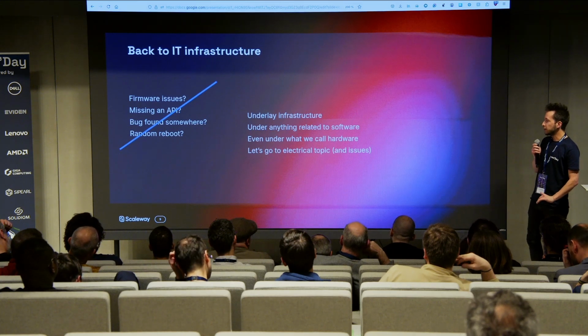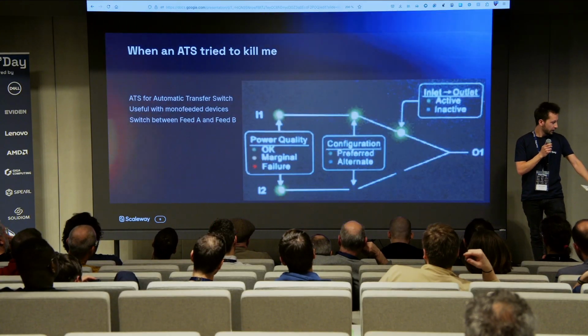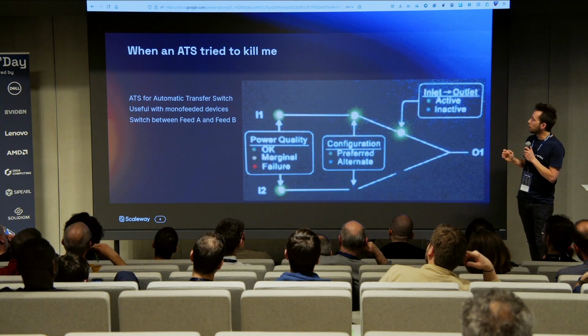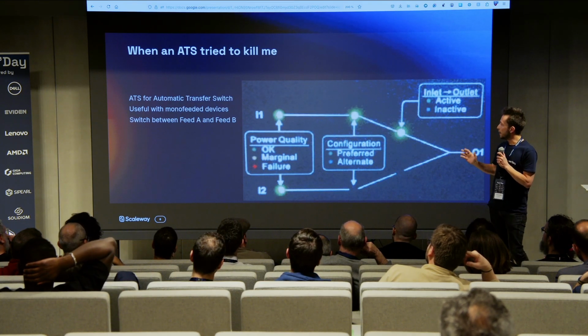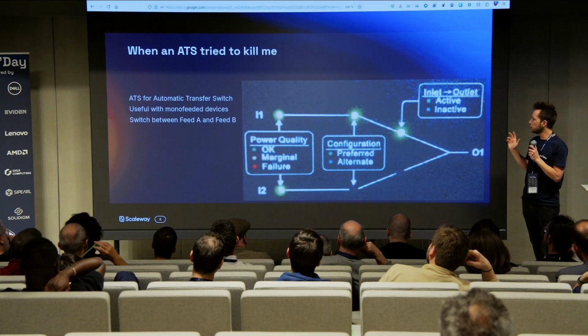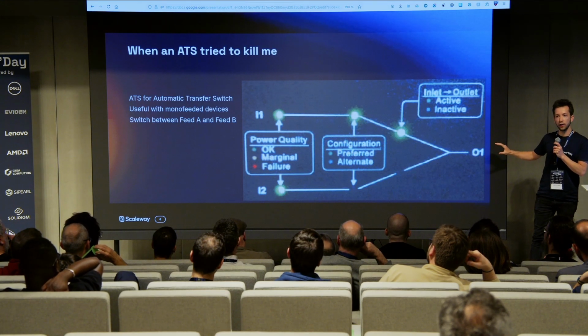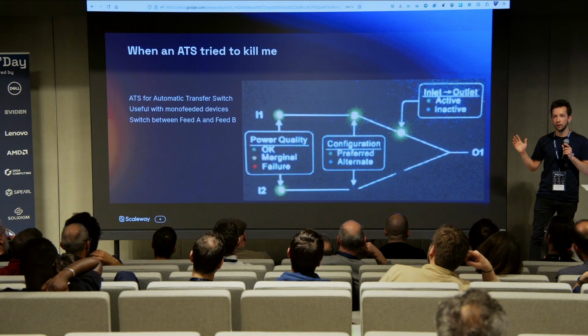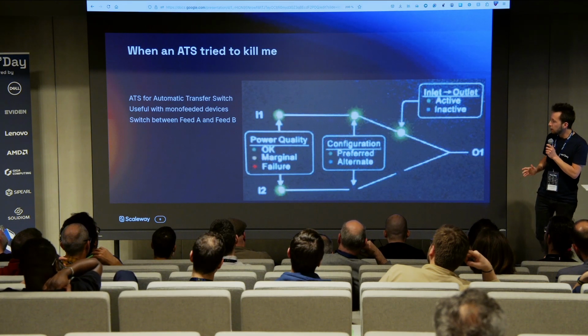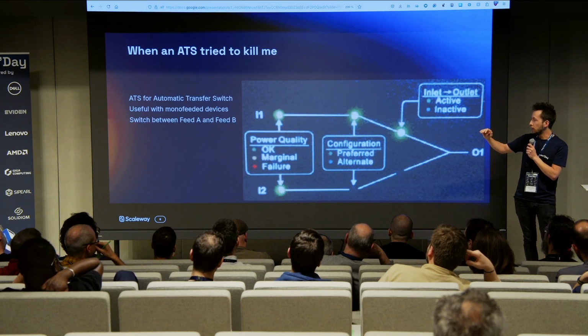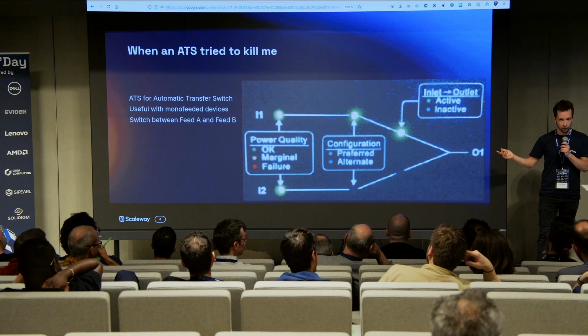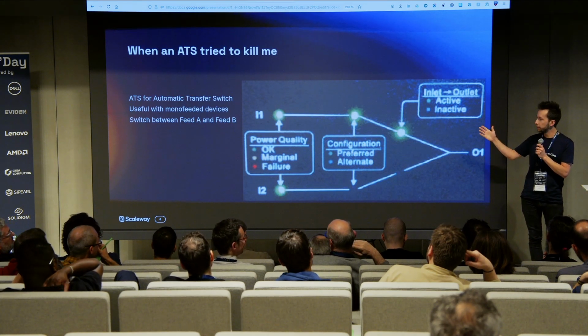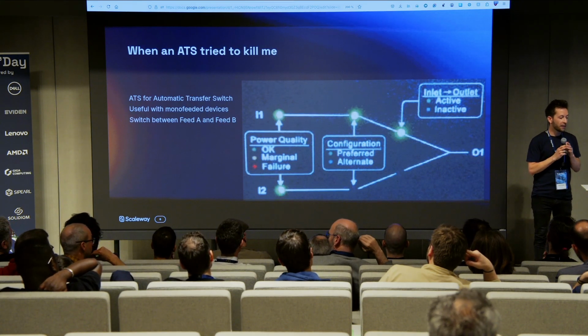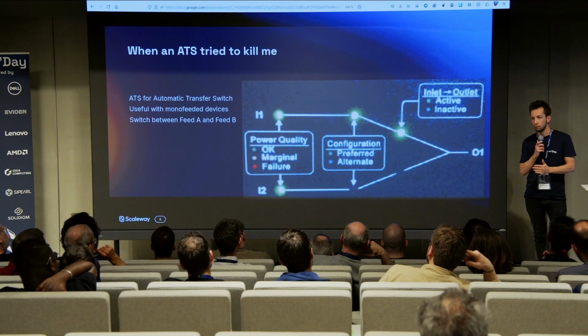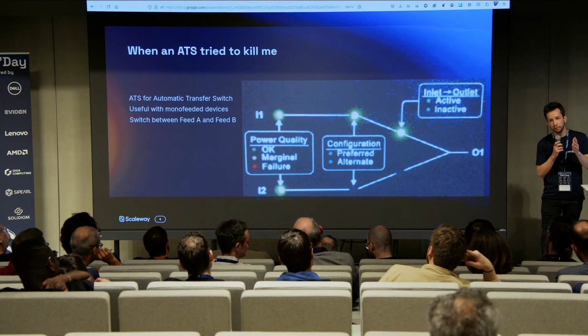Under, let's go to electrical topics. And still related to luck. Just in case, an ATS is useful when you have a device with only one PSU, but you still want to be A/B redundant across two feeds. So you are powered by only one feed at a time, but if this feed fails, it switches fast enough to avoid a cut, in a couple of tens of milliseconds.